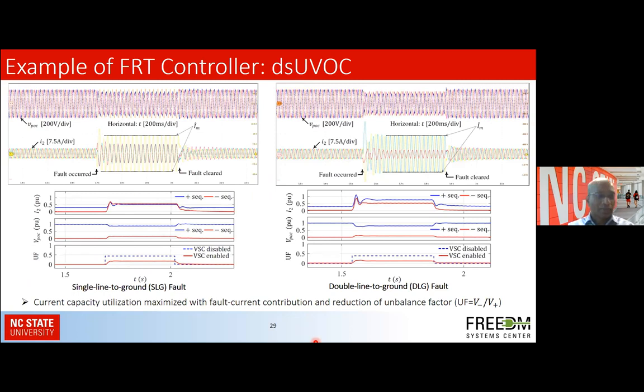So the results here, the key features are here. Once it enters the fault mode, both the positive and the negative sequence components are injected. And here it shows the negative sequence is 0, and then how it picks up once it enters the fault mode. So one important aspect of this controller is to improve the unbalance ratio. With the injection of the negative sequence components, we are able to minimize the unbalance factor, which is the ratio of the negative sequence component over the positive sequence component. And it's shown here for both the single line to ground and the double line to ground.